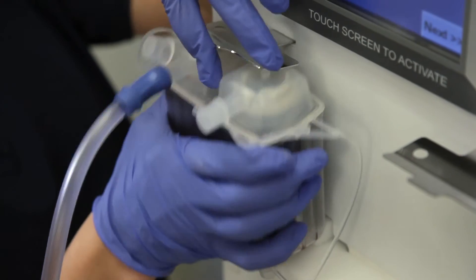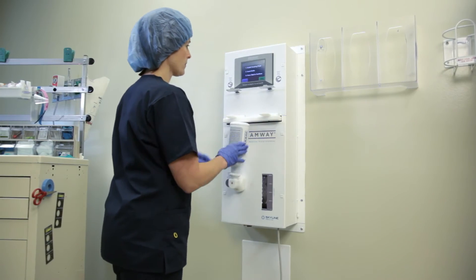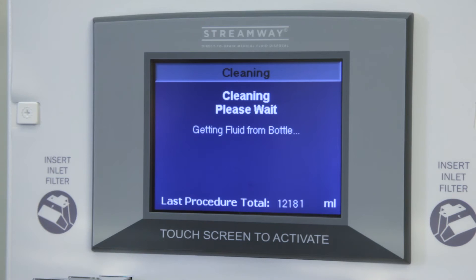When you're done with the procedure, you remove the filter, attach the Streamway System cleaning solution, and press start. The device automatically cleans itself in less than five minutes and is ready for the next patient.